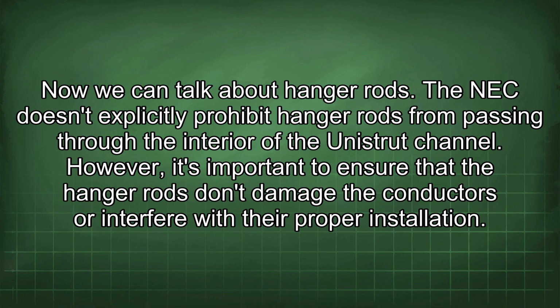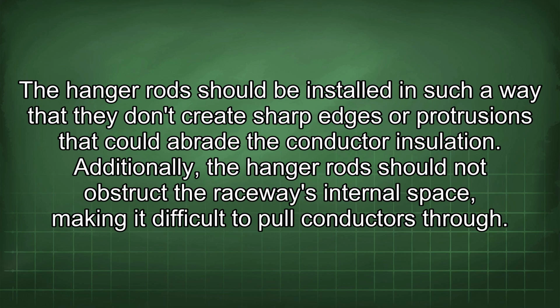However, it's important to ensure that the hanger rods don't damage the conductors or interfere with their proper installation. The hanger rods should be installed in such a way that they don't create sharp edges or protrusions that could abrade the conductor insulation.